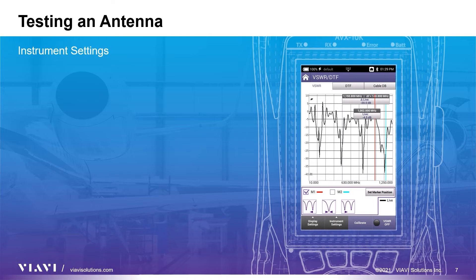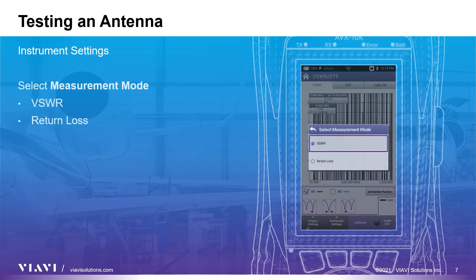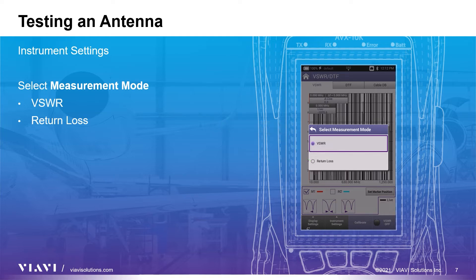With calibration complete and cable type selected, you are ready to test either an antenna or a cable. Let's look at testing an antenna using the VSWR tab. An antenna can be tested using a measurement mode of either VSWR to view readings as a ratio, or return loss to view readings in dB.